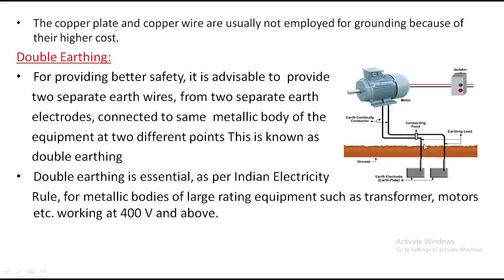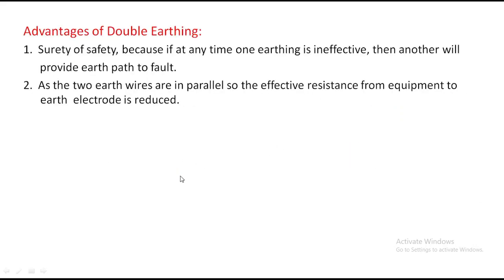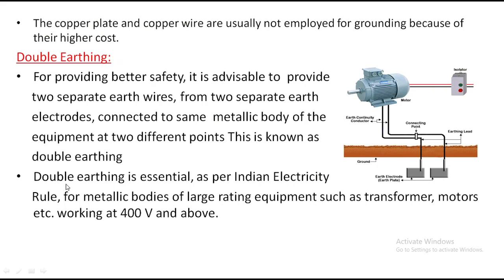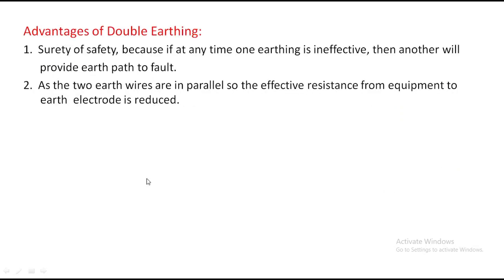Equipment is earthed at two different points. This is one point and this is the other point. This is known as double earthing. Second, double earthing is essential as per the Indian Electricity Rules for metallic bodies of large rating equipment such as transformers, motors, etc. working at 400 volts and above. So double earthing is generally preferable. Any motor or machine working at 400 volts and above, double earthing is more preferable. So this is about double earthing.